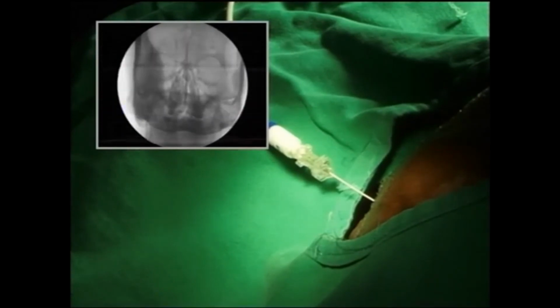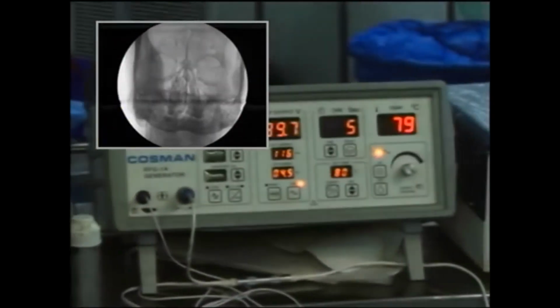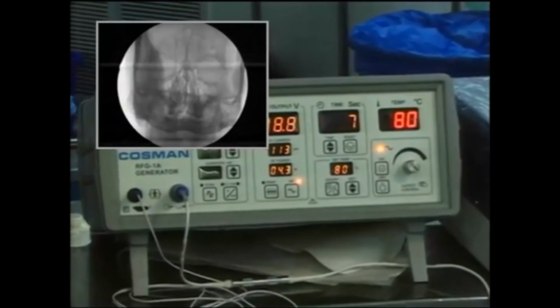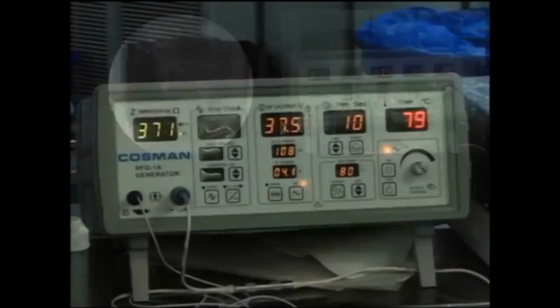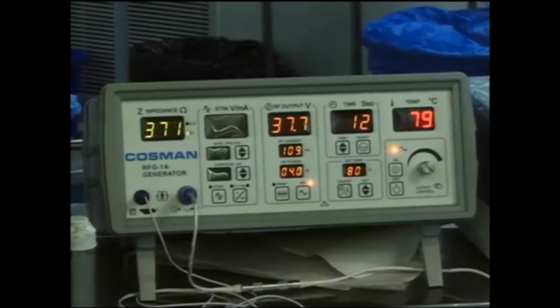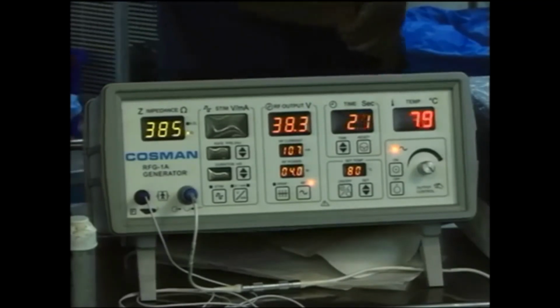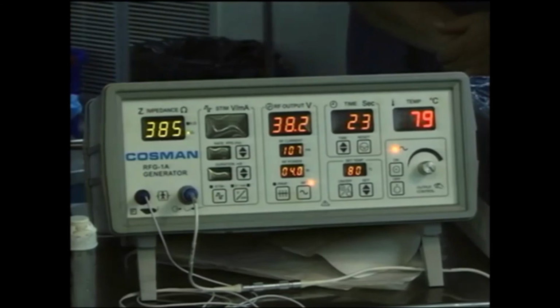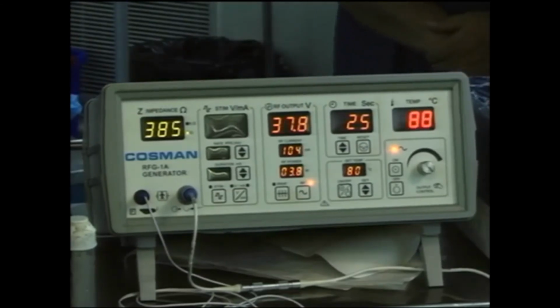Yes. What we do once it is going, you see, look at there. Once the actual temperature is reached, then only we take a reset and then again start counting. So the actual time we are keeping is around 70 seconds, not exactly 60 seconds. Initially when the temperature is rising, it takes around 10 seconds, and once the temperature has reached the desired set temperature, we put the reset button, and then the counting of the seconds starts again. That means the actual timing at the 80 degree is 60 seconds. It is not less.